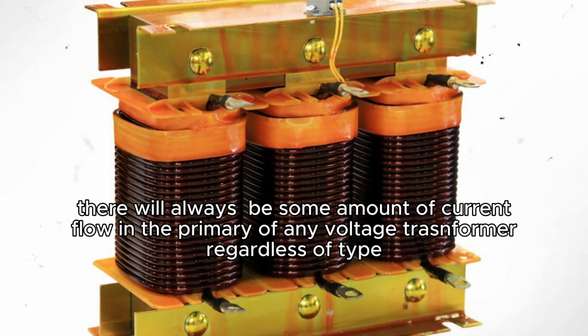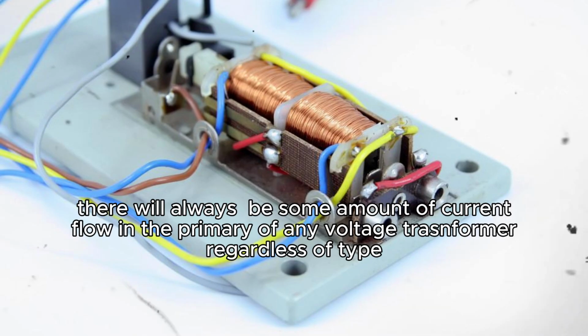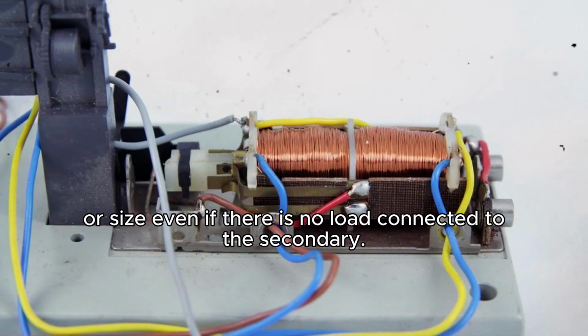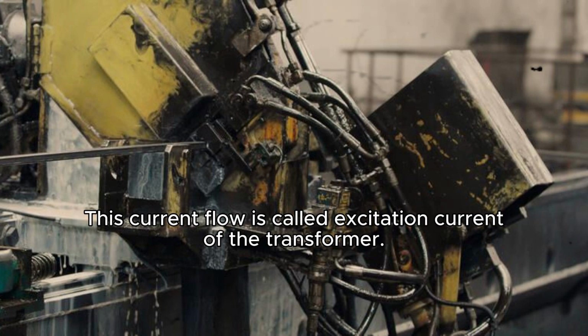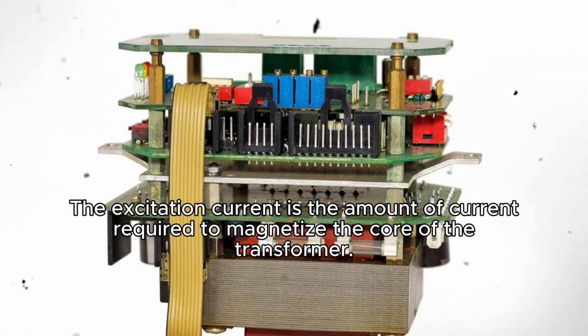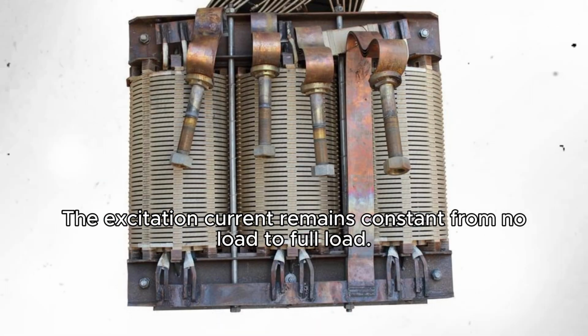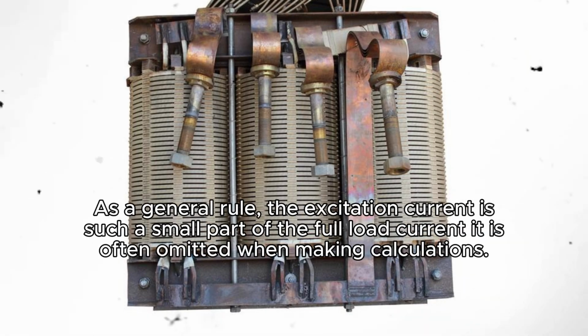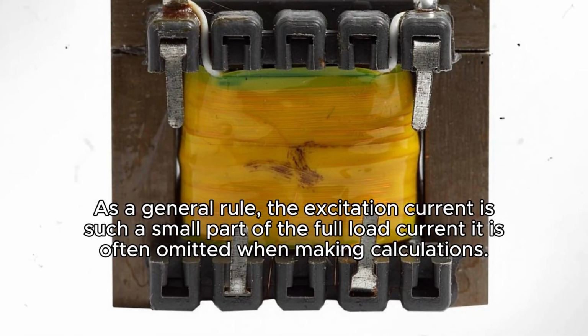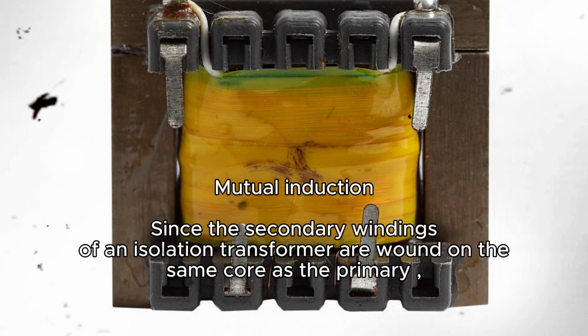Excitation current. There will always be some amount of current flow in the primary of any voltage transformer regardless of type or size, even if there is no load connected to the secondary. This current flow is called the excitation current of the transformer. The excitation current is the amount of current required to magnetize the core of the transformer. The excitation current remains constant from no load to full load. As a general rule, the excitation current is such a small part of the full load current it is often omitted when making calculations.